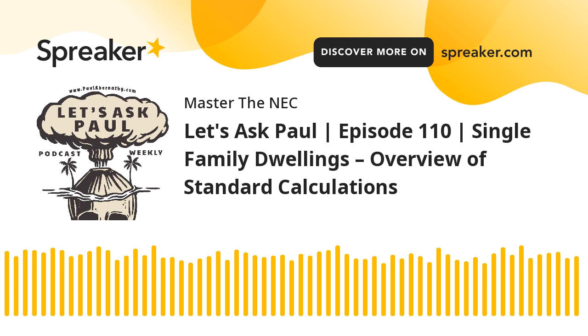So that's what that means. But if note 3 doesn't apply, then you're going to stick with column C and follow those values. And then, again, if it's just 12 kW or less, you're just simply going to pull from the table. For example, if I had a 12 kW range in my calculation, I'm just going to use 8 kW because column C is actual demand values. And if you look under one appliance, it says 8 kW. So it doesn't matter in the standard method if that range, for example, says 12 kW. In my load calculation, I'm just going to use 8 kW.